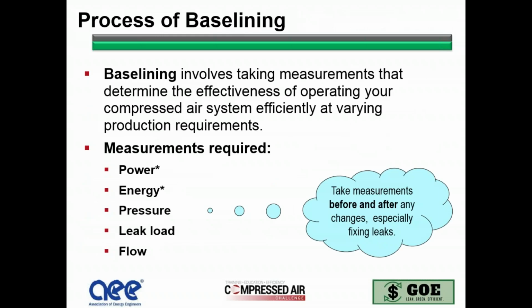So baselining. The process of baselining really involves taking measurements and determining the effectiveness of the operating system for the compressed air, under various production requirements. That means measuring the power, energy, pressure, leak load, and flow. Taking measurements both before and after changes is really important. Why? The real key there is to see if the efficiency improvements actually happened. When you made the changes, did you get the results that you expected? And if not, what was the reason?